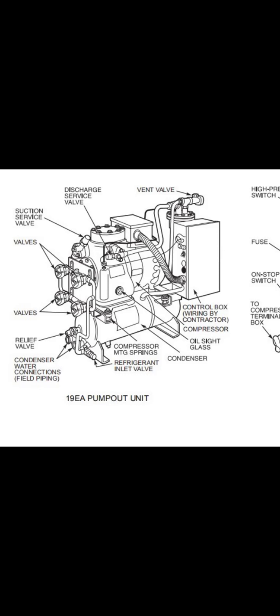So this cool water valve, which was closed, gives cooling to the hot gas going into the condenser. Now you open this valve. What happens? The gas will convert into liquid and go into the condenser. Slowly they will take all the vapor, and you will see the pressure go down in the gauge from condenser, cooler, evaporator. When it comes to before zero, we check by hand; some little pressure, 1 or 2 psi.